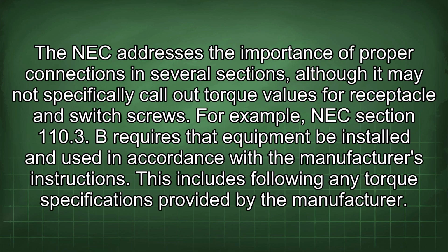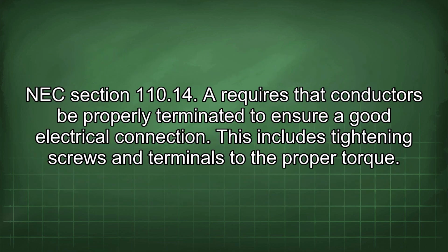The NEC addresses the importance of proper connections in several sections, although it may not specifically call out torque values for receptacle and switch screws. For example, NEC section 110.3(B) requires that equipment be installed and used in accordance with the manufacturer's instructions. This includes following any torque specifications provided by the manufacturer. NEC section 110.14 requires that conductors be properly terminated to ensure a good electrical connection. This includes tightening screws and terminals to the proper torque.